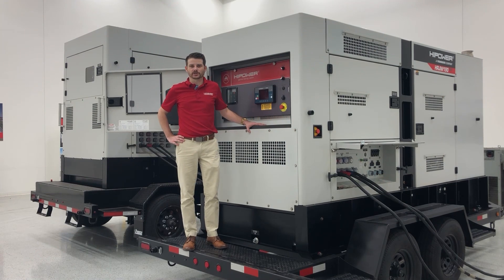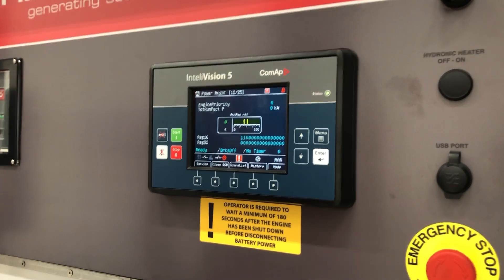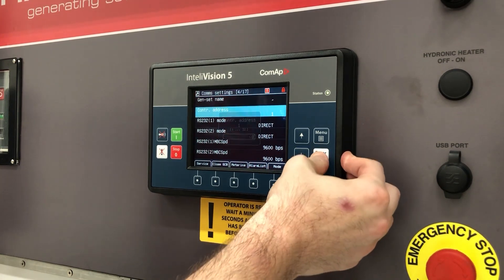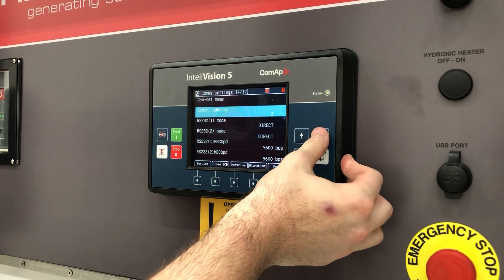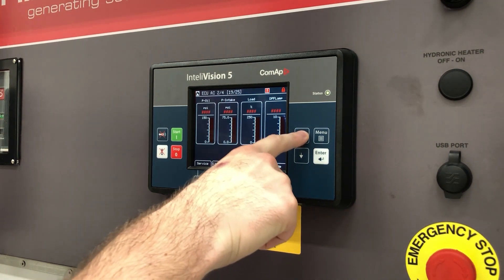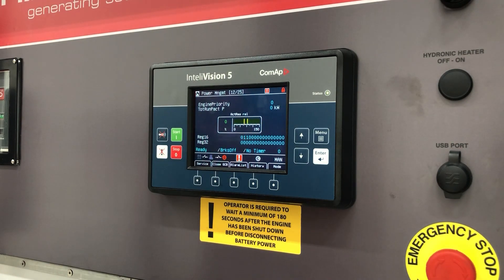Now that we have our generator mode selected, let's take a look at the controller address. This set point will be modified through our ComAp InteliVision 5 controller. To start, you will press the menu button, go to set points, and scroll down to communication settings. Here you'll see a controller address and you can set this to any value between 1 and 32. Once you've changed it, you will need to recycle the power. Once the controller has turned back on, you will press metering, scroll to page 12, and if everything has been done correctly, you should see the values on the screen have changed to the corresponding positions you have set your controllers to. This indicates that the generators see each other and are ready to work in parallel.